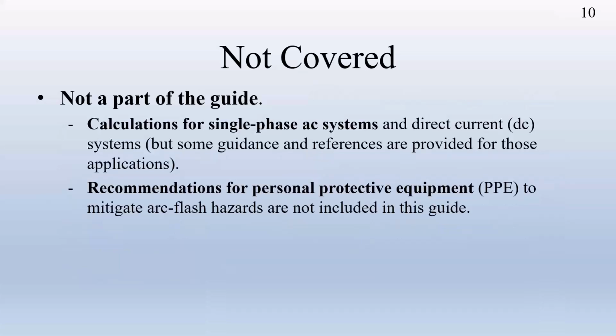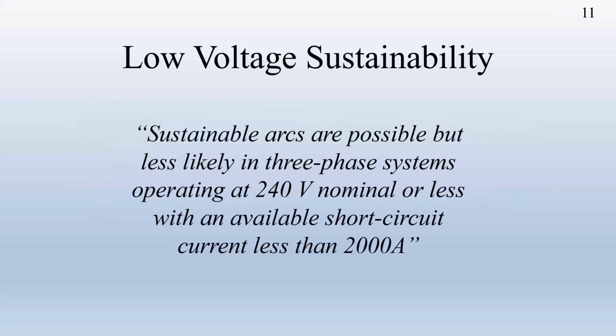As I have mentioned, this is only for three-phase, so it doesn't cover single-phase AC systems. We didn't provide it because you can extract it from the three-phase, and in the 1584 2018 they also provide some guidance for possible application to single-phase. It doesn't cover DC either. It also doesn't cover the personal protection equipment, the PPE side, because when you try to determine PPE, in addition to the arc flash you have some other considerations. So the recommendation for PPE is not in this guide.